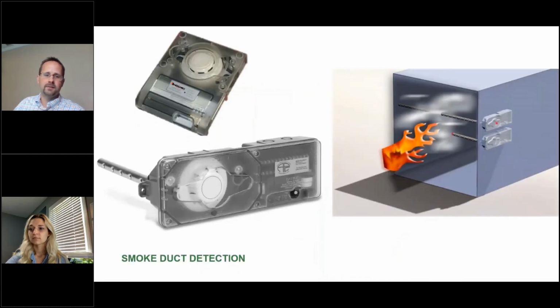All right, so here are the different types of duct detection. There's no one way to do it. The code talks about different areas. The most common is to have the smoke detector at the damper, within 5 feet of the smoke damper, and that's going to be the most common that we'll see. But there are options: if you have a full smoke detection system, you can use that to close your dampers, though a lot of facilities don't because that's really expensive. And if you're going across a corridor door, there are options there. So if you're trying to minimize cost and already have detectors everywhere else in the building, there are things you can do. But for the most part, they need to be within 5 feet of that smoke damper to operate.